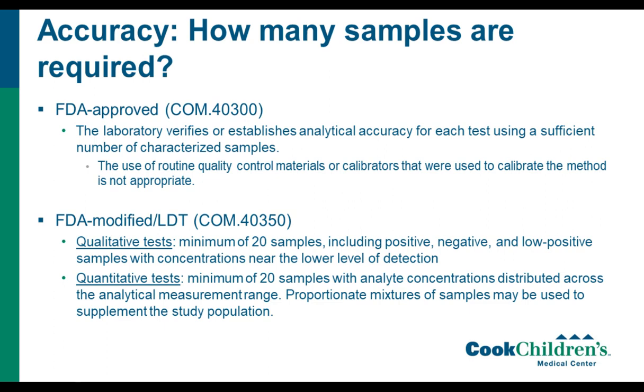It's a minimum of 20 samples, but they say it must span the analytical measurement range, which is basically the range of the assay. So if your assay goes from 500 to 5 million, you want to have samples that fall across that curve and not just all of them falling around 50,000, for example. And you can use mixtures of samples if you need to get some of the concentrations that you need.